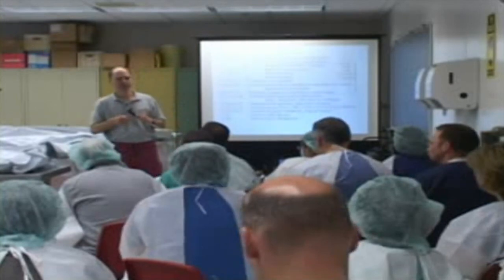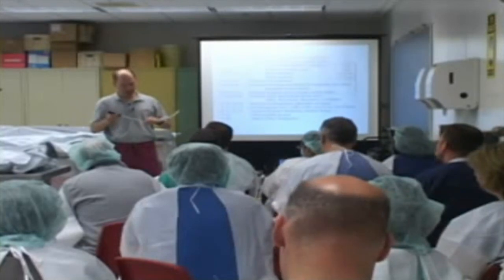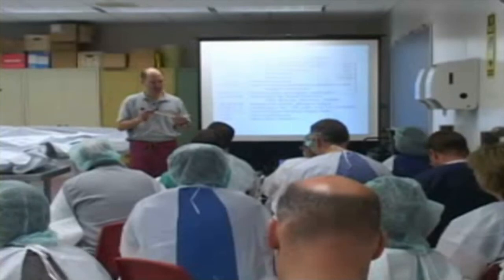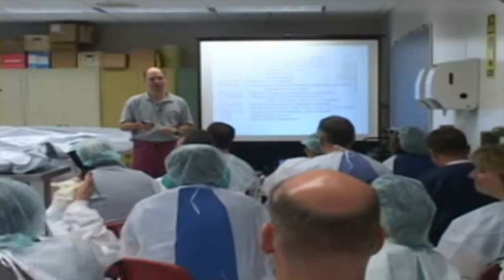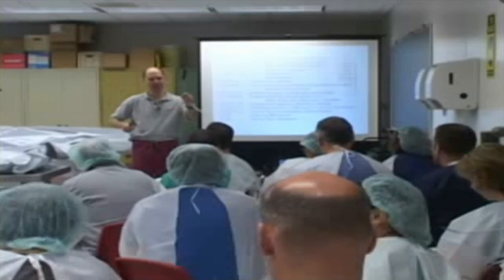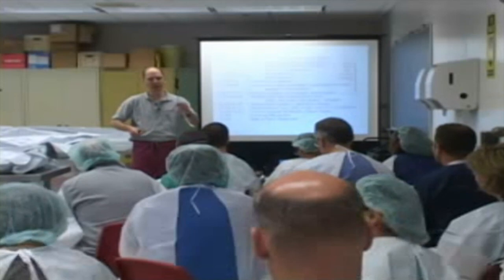Q: Are these just sterilized? A: They're cleaned with a Cidex soak or a Steris soak — glutaraldehyde for 20 minutes. You can also run it under water, wipe it down with a betadine sponge brush, and rinse it, but the formal recommendation is a 20-minute Cidex soak. You can soak everything except the laryngoscope light; the eyepiece and all other components go into glutaraldehyde.